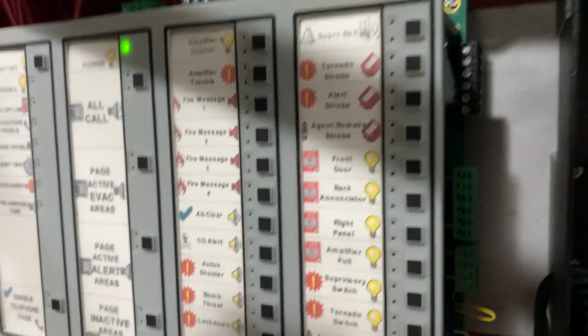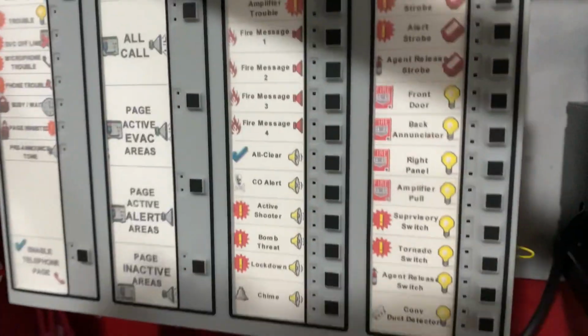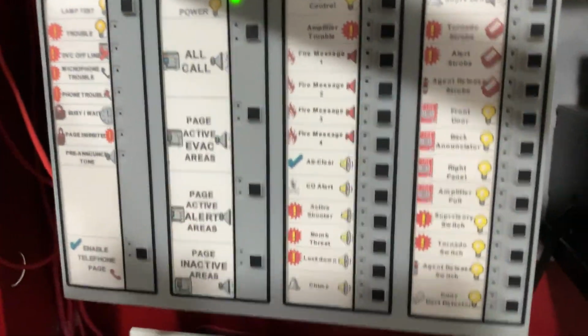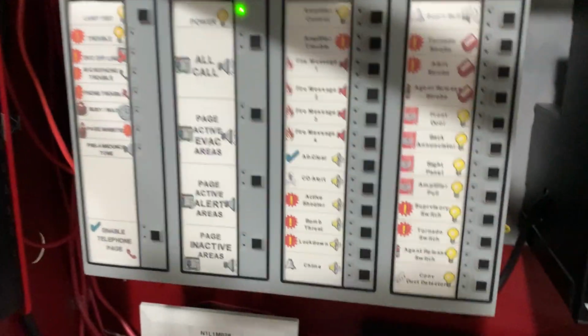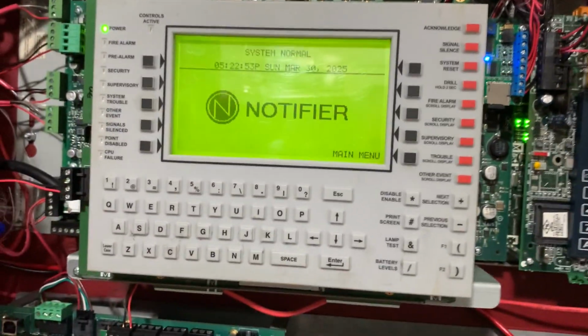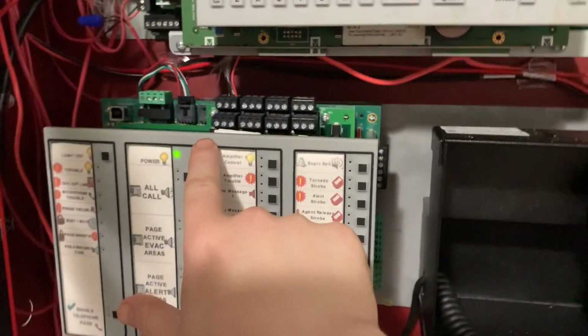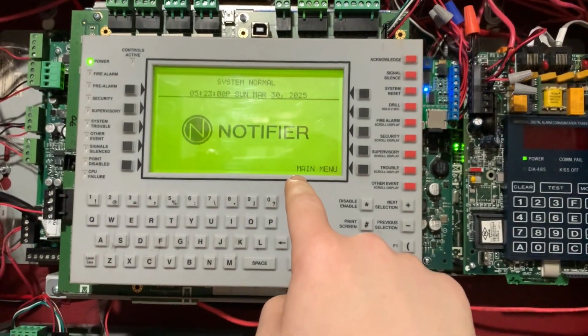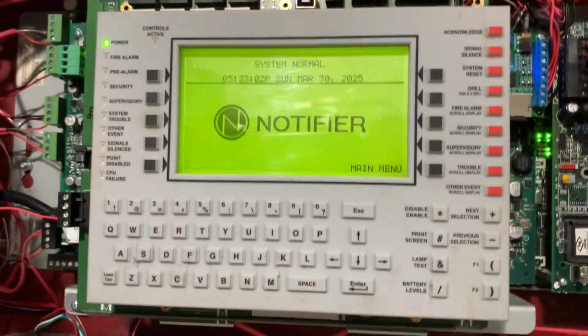And if I open up the DVC's address panel, you won't be able to see it, but there's also an NCM behind the DVC right there. Sorry, you're not able to see that. But the DVC is also connected to an NCM-W. So I've got a total of 3 NCM-Ws on the system, one for the DVC, one for the 640, and one for the NCA-2. All right. And the 640 is node 1, DVC is node 2, and the NCA-2 is node 3. So now my system is multi-networked.